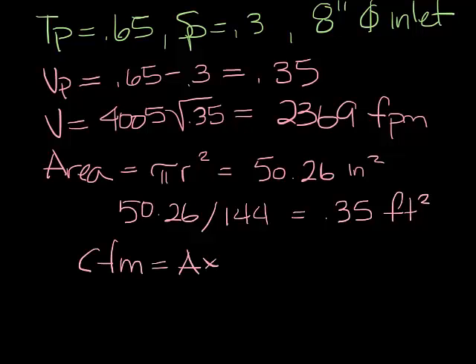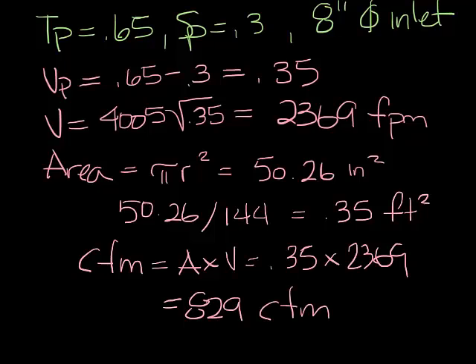So now the CFM is the area times the velocity, which equals 0.35 times 2369 feet per minute. And you get a CFM of 829 CFM.